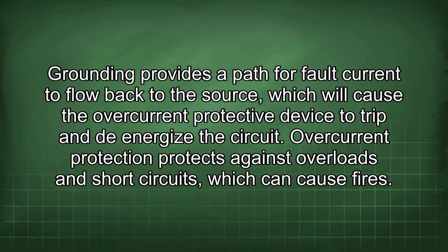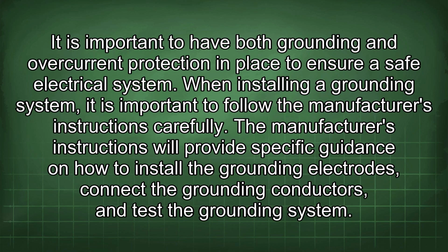Grounding provides a path for fault current to flow back to the source, which will cause the overcurrent protective device to trip and de-energize the circuit. Overcurrent protection protects against overloads and short circuits, which can cause fires. It is important to have both grounding and overcurrent protection in place to ensure a safe electrical system.